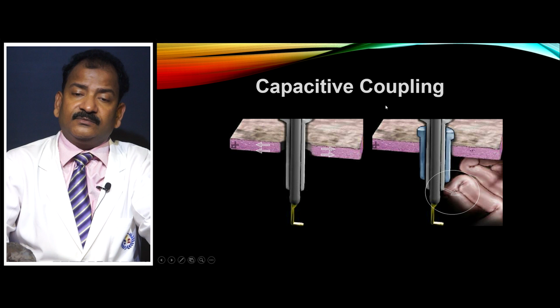Another good thing is that there is an active electrode monitoring system. There is one company whose name is Encision. They have made a beautiful adapter. This adapter will keep on examining your instrument, that is called AEM technology, active electrode monitoring system. So if your instrument has insulation failure, if your instrument is doing direct coupling, if your instrument is doing capacitive coupling, it will give you an alarm, it will become red and it will break the circuit. So this is the instrument and it is a burn protection system.